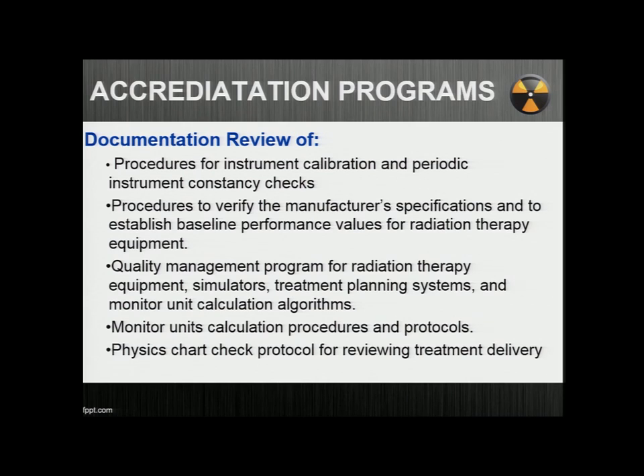So when we do instrument calibrations, we changed our practice. That was probably 11 years ago, at my center. We changed our practice so that now they're in the habit of documenting not only the serial number of the instrument I used and when the last calibration date was, but most importantly, what the efficiency of that device was. Do I do that because I want them to have practice handwriting? No. They do probably 8 patients a month that they need to document this with, because it reminds them that, had they looked at the efficiency of one probe versus the ion chamber, it would have been very clear, very intuitive to them, that this device isn't really what I should be looking at for this particular procedure.